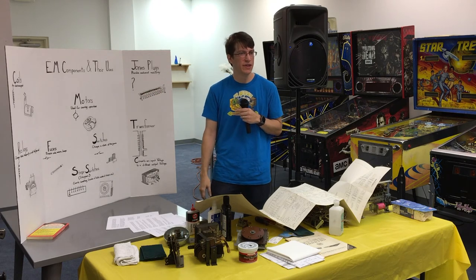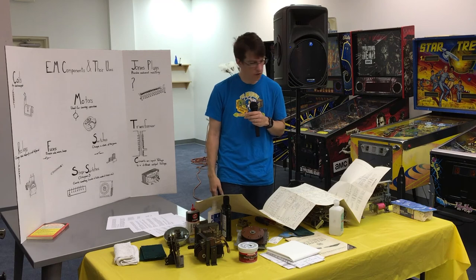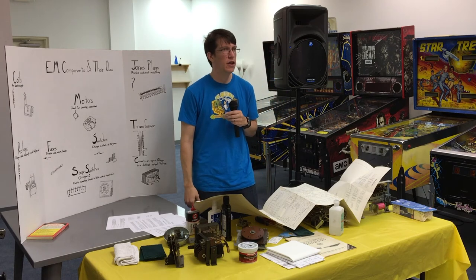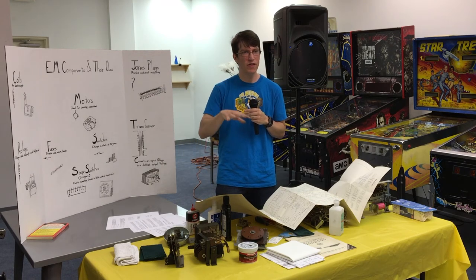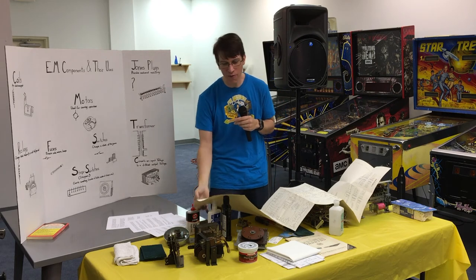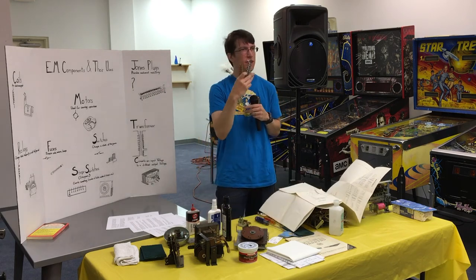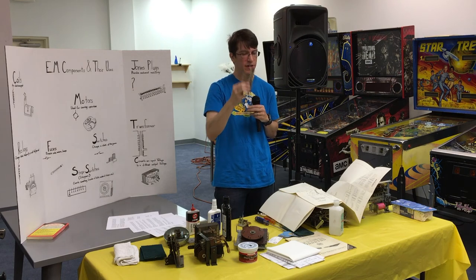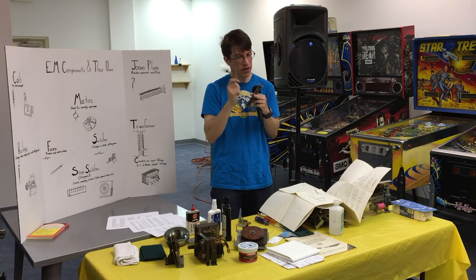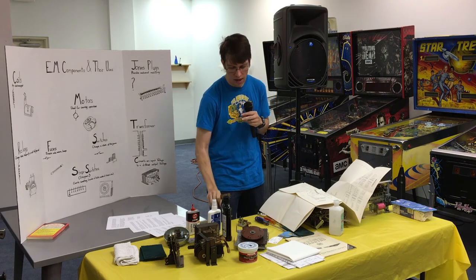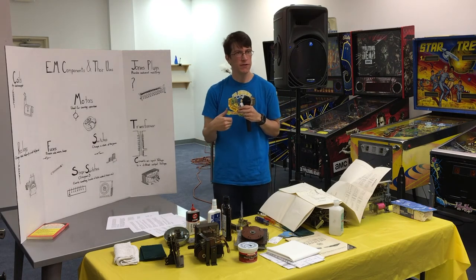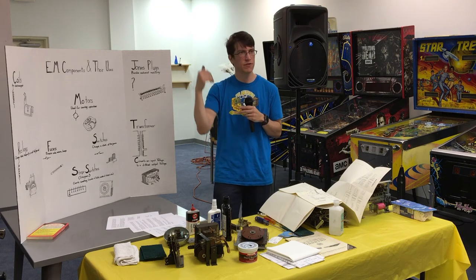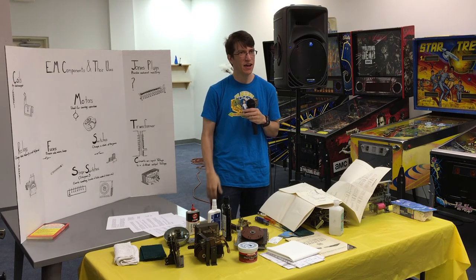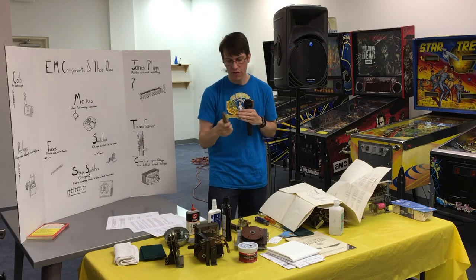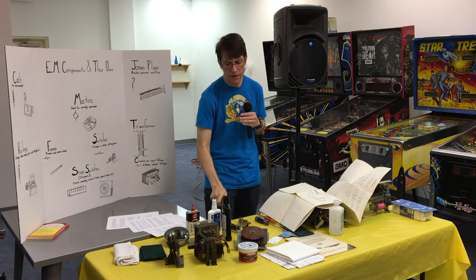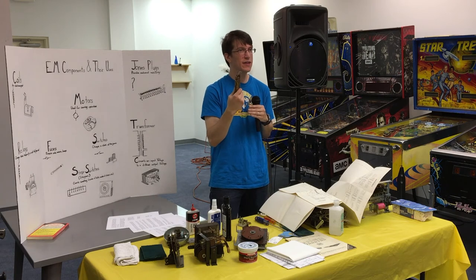There's no symbol. If you're lucky, certain manufacturers will have a plug chart. The plug chart will represent one side of the plug - not incredibly helpful if you've got 24 wires coming off and coming on. So that's 48 wires which are undocumented. To make life even more difficult, the wire colors can change from the male to female side. So it's important that you're reasonably certain that these things are clean.